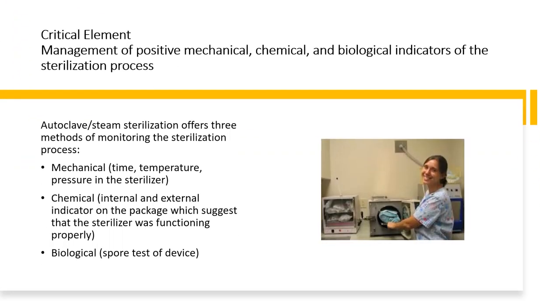This added critical element is for management of positive mechanical, chemical, and/or biological indicators of the sterilization process. This process includes the following: mechanical, which is time, temperature, and pressure in the sterilizer; chemical, which is internal and external indicator on the package suggests that the sterilizer was functioning properly; and biological, which is spore testing of an autoclave steam sterilizer. This must be performed at least monthly with documented results kept on site, even if the unit is not used monthly.